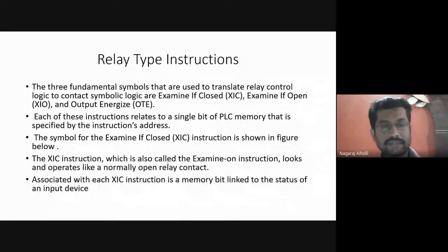The XIC instruction, which is also called the examine on instruction, operates like a normally open relay contact. When the relay contact is normally open, it is in the open state. When you energize the relay, when you pass suitable current through the relay, what will happen? The contact will get closed and the current flows to the other part of the circuit. This XIC instruction is similar to the normally open relay switch.